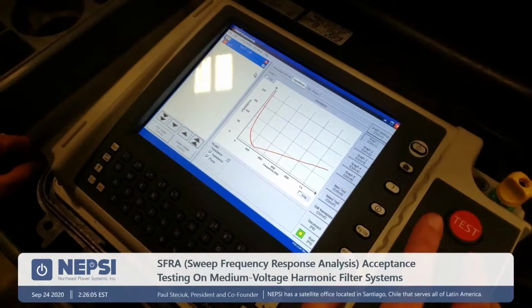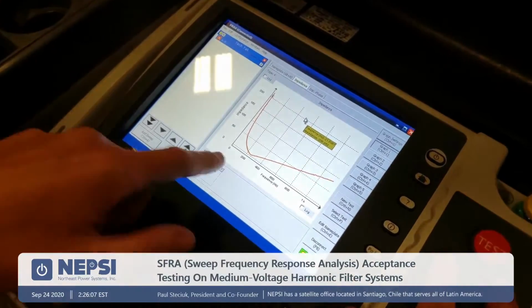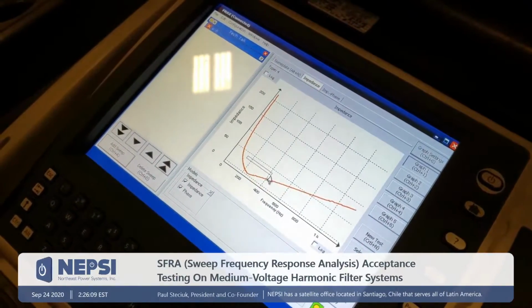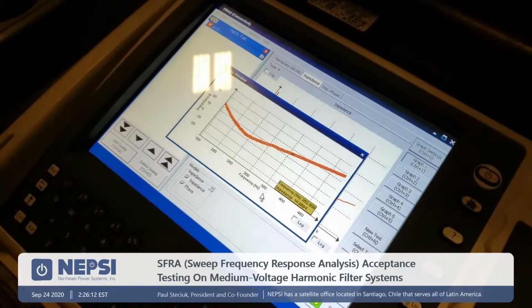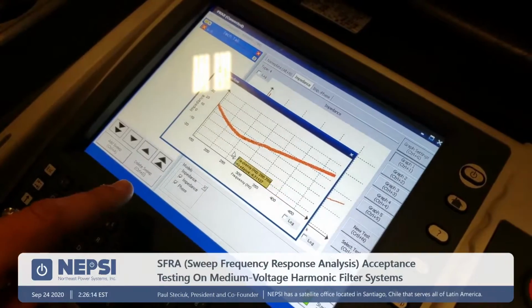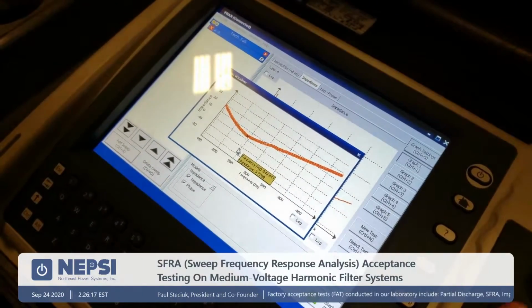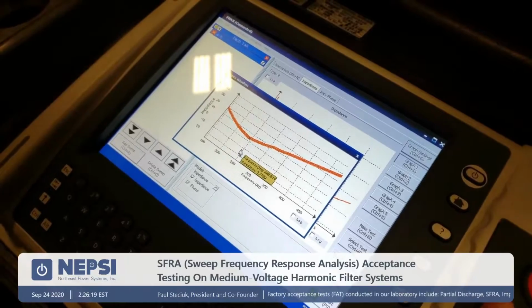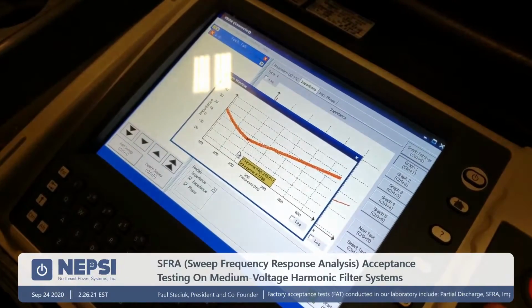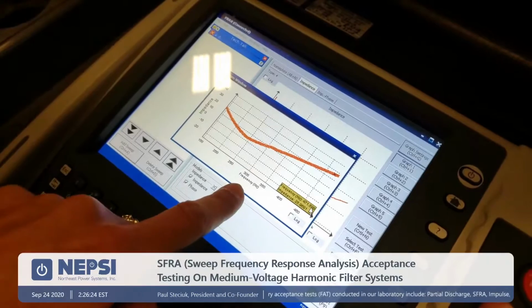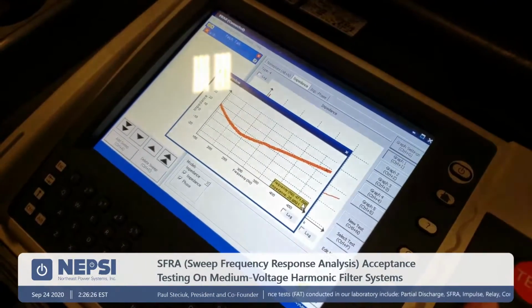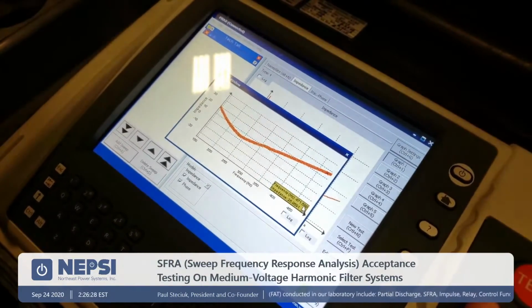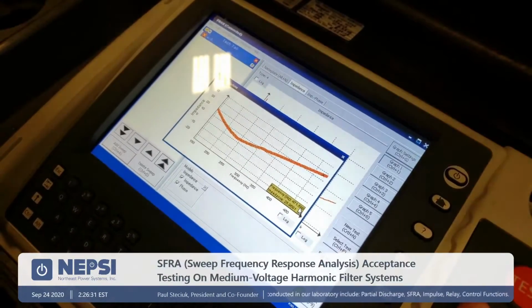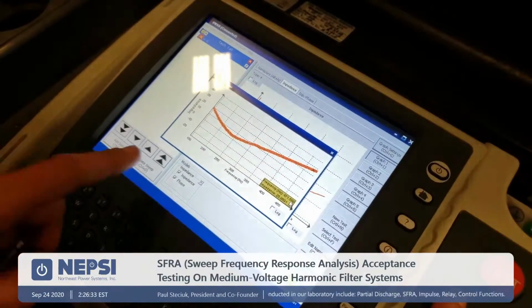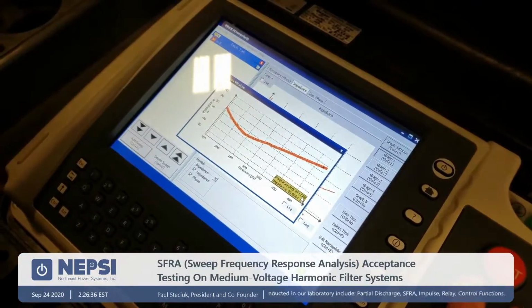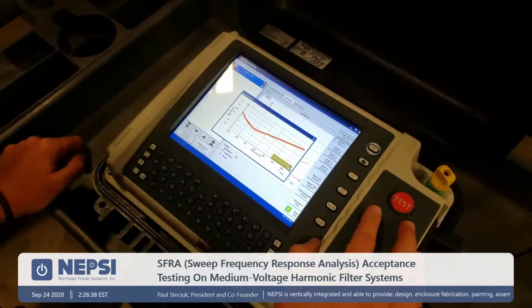So what do we have here? Right here, the test is complete, and this goes down to around 235 hertz, which is 4.7 tuning point, because all the reactors, all stages in this bank are tuned to the 4.7th harmonic. And here it's in frequency, in hertz, not in the harmonic number. Because it's a 50 hertz system, if you multiply 4.7 times 50, you'll get the tuning point where it should be, which is the low point of the impedance.